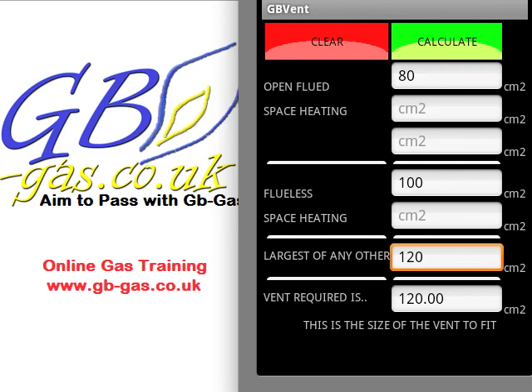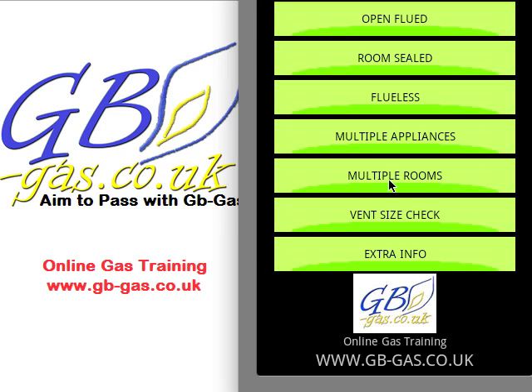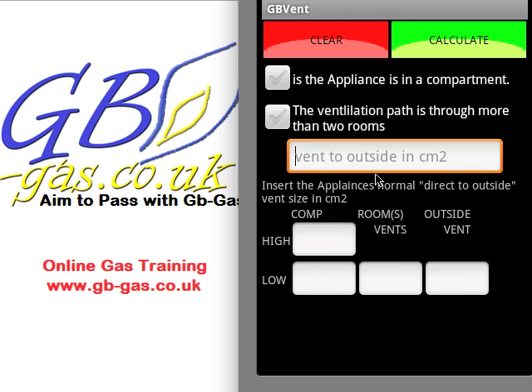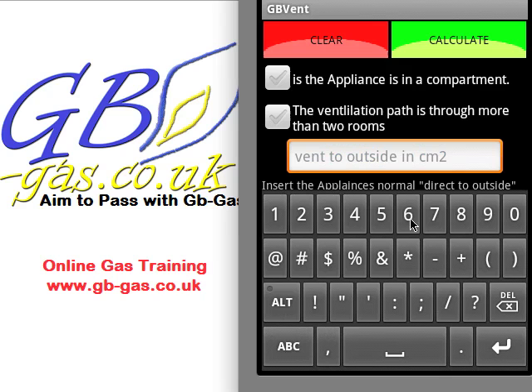Hitting the back button again, we can now look at multiple rooms. This is generally for open flued appliances but can be used for flueless appliances as well — where I can't get out of the room in a straight clear path and have to go through maybe a corridor and through another room. We need to know what size of ventilation is required for the appliance fitted in that room, so in this scenario we'll suggest the boiler needs 56 cm².